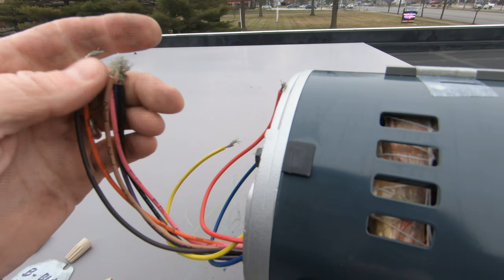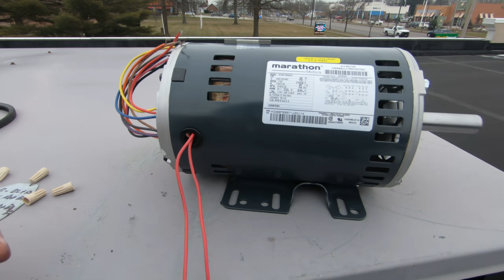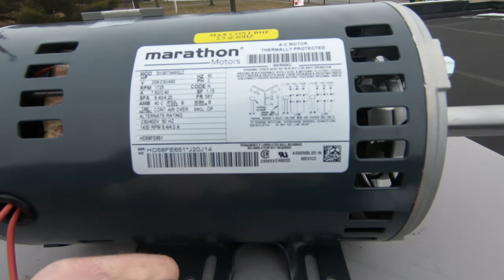As long as you're wired up according to that and your phasing is correct, you'll be good to go. If your phasing's off, your motor will run backwards. That's why I wrote down which 2 color wires my power supply was connected to, so it'll make my phasing right. I won't have to reverse the rotation by getting back into the electrical compartment or switching it at the contactor when I replace that. So I'm gonna go ahead and get this thing wired up. It's pretty self-explanatory, all your info is right here.